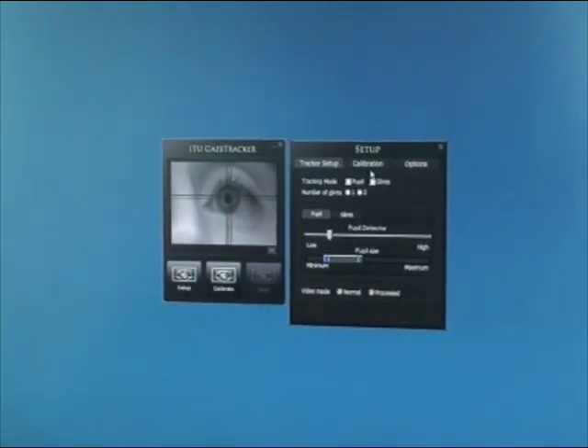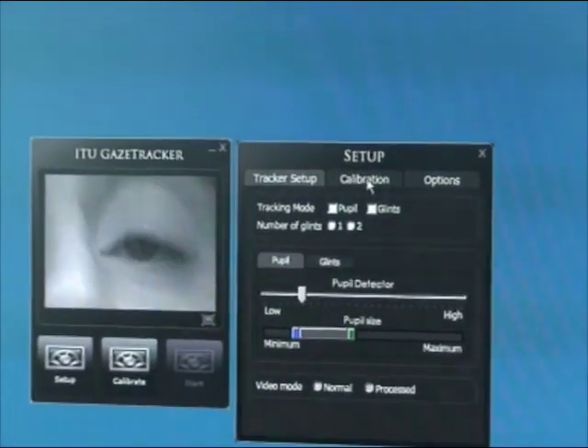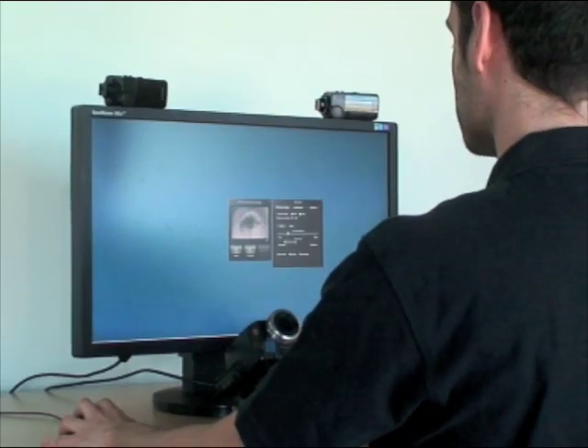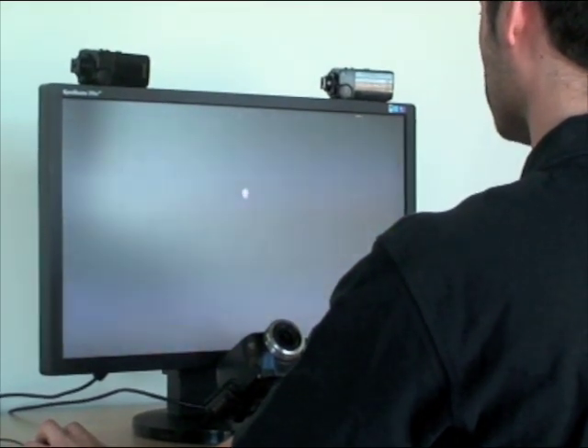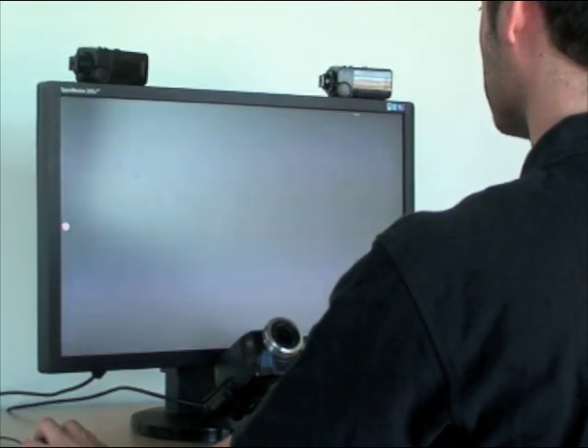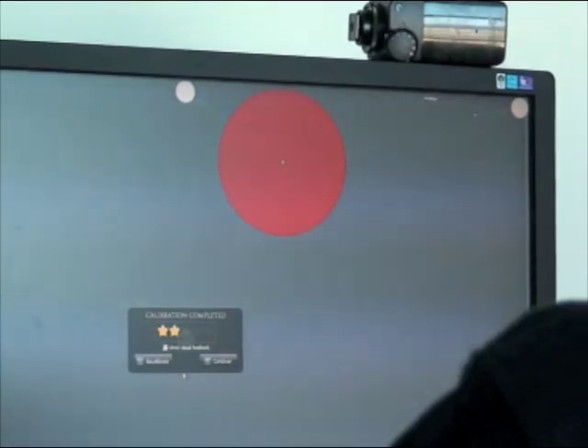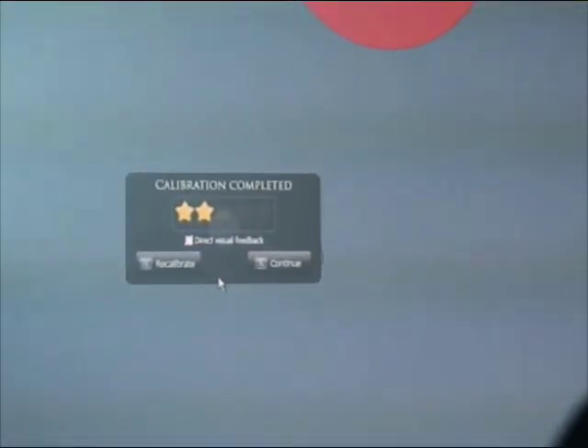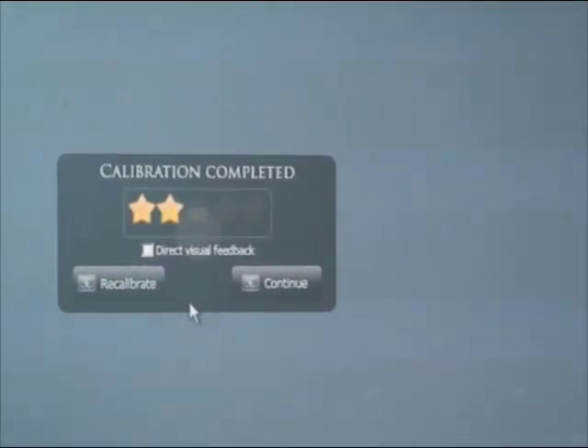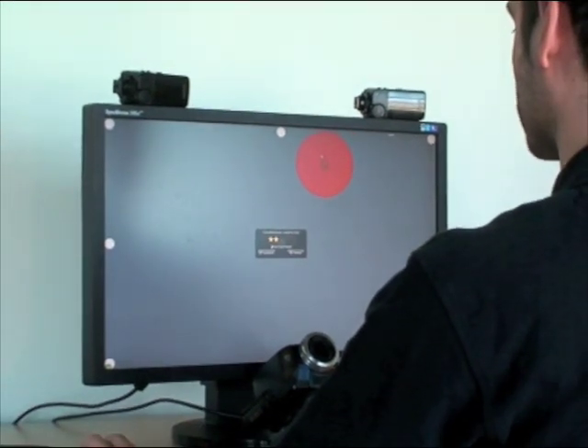We need to calibrate the system in order to be able to estimate gaze. We can launch the calibration by clicking on the calibrate button. This will show some points on the screen that the user has to follow. Once we have calibrated, we get the calibration results window. The calibration targets are shown on the screen together with circles that represent the calibration results.